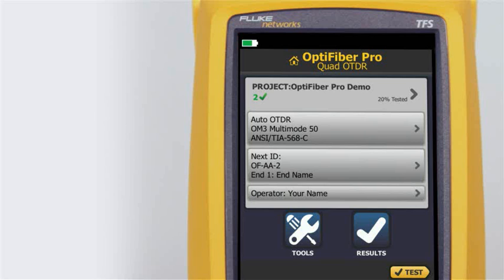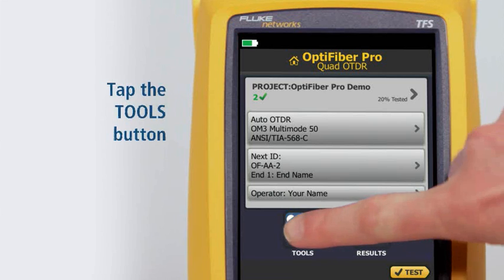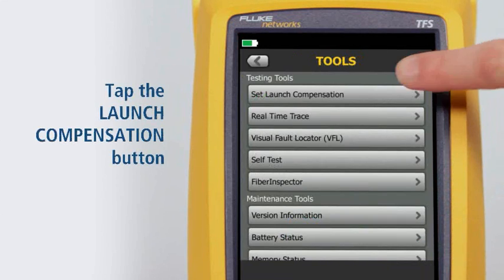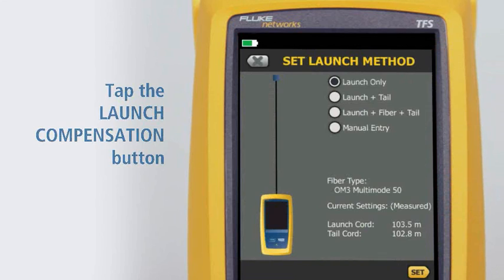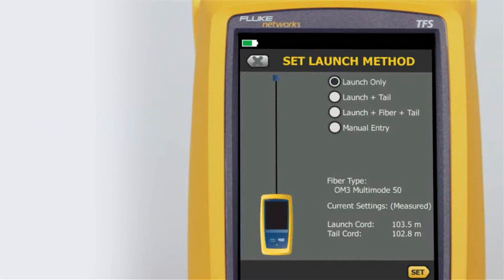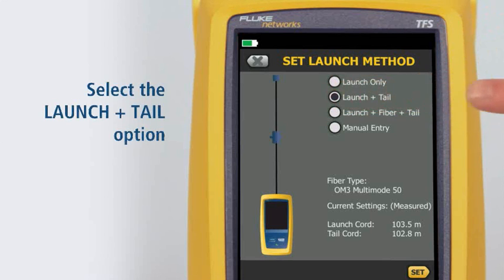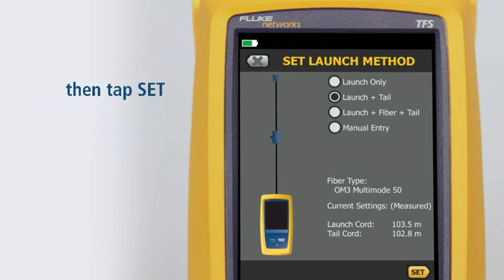To set launch tail compensation, first tap the Tools button. Tap the Set Launch Compensation button. It's important to use a launch and tail cord when testing with an OTDR. The only way to measure the last connector's properties is to connect it to another fiber with similar properties. Therefore, we will choose the launch and tail option. Then tap Set.